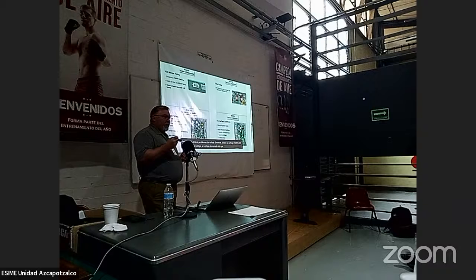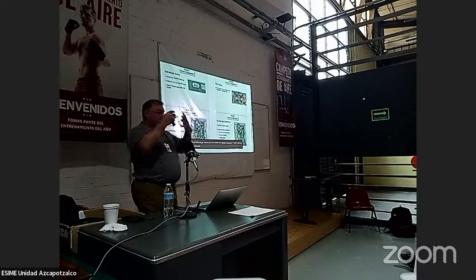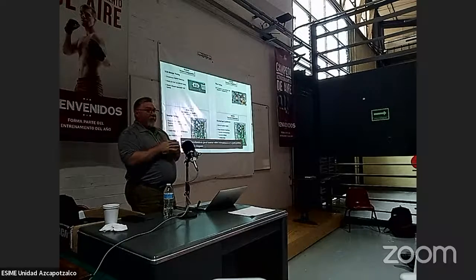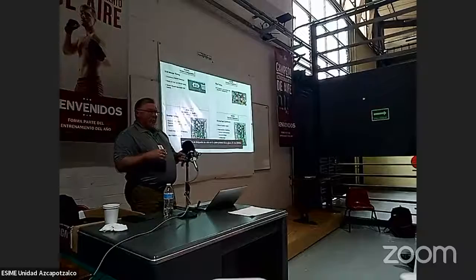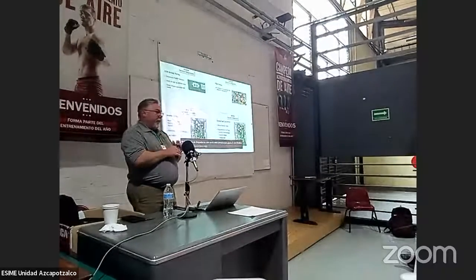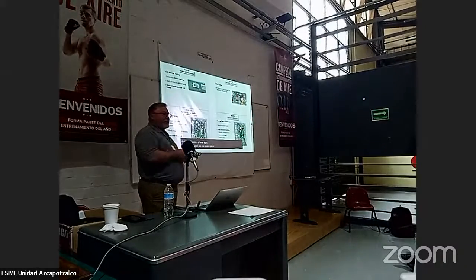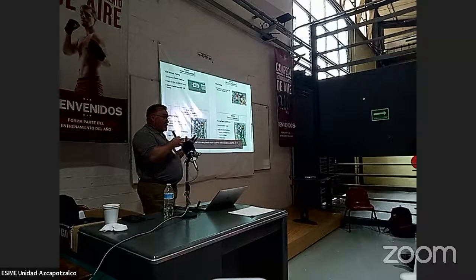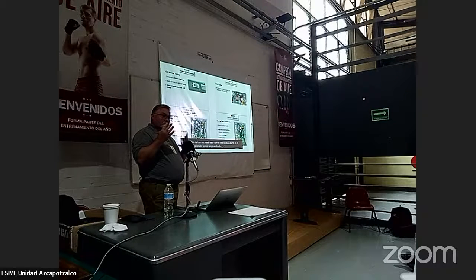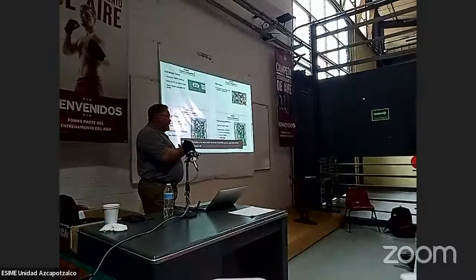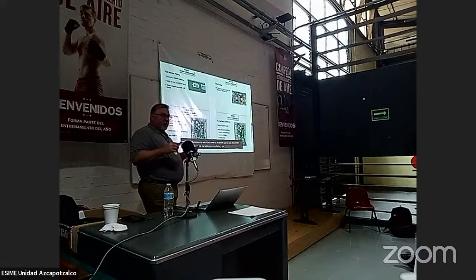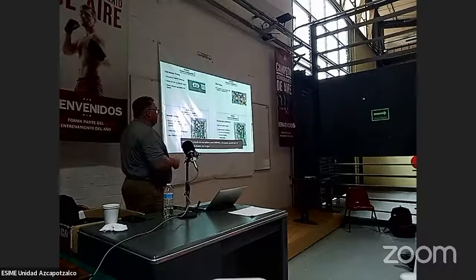Inverter fallback: you've got temperatures that are too high on the discharge line, and it's going to create that coming back, right? Another thing that could be happening is inverter over temperature. On the back of the board is a heat sink. If that heat sink is dirty, or if there's something wrong with it, that could cause the board to overheat. If the fan is not operating at the right speed, you may not be moving enough air across that board to cool it down. That can cause the inverter over temperature. So there are several things that can cause that problem.